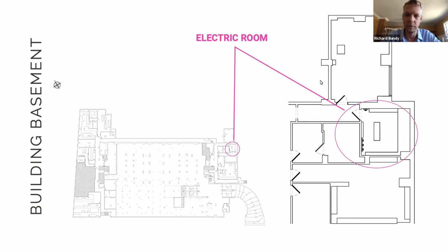The electrical room itself is, I would say, fully booked up. You have a large transformer sitting in the middle of the room, and around all the walls you have various meters and distribution gear. So it's not going to be possible to install the automatic transfer switch or likely the dedicated export meter in the electrical room itself. We'll probably have to put it in the hallway outside or in the room just to the north. Can we have the next slide, please?